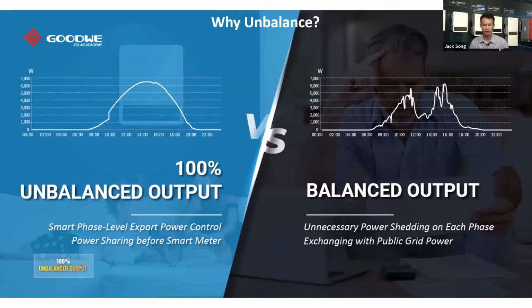From here we can see clearly how the unbalanced output and the unbalanced charge function can help to increase the self-use and the solar production. This is the comparison between the systems with unbalanced output and without unbalanced outputs, of course with a zero export function. We talked about this first. Unbalanced outputs, like I said, especially in scenarios with a zero export power limit requirement, on each phase they cannot export to the grid, right? So the production from the solar inverter, after the consumption of the loads on each phase, has to follow the lowest power of all the phases.